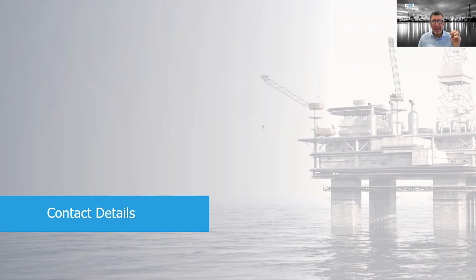They asked, do the glands have to be certified? If I remember correctly, this is somewhat of a sticking point. For circuits that contain a single IS circuit, meaning if we have a junction box with a single circuit coming in and a single circuit going out, the standard does allow you to use, and I want to double check this, basically the requirement of the gland is that it has to meet the impact requirements of 60079-0 and all that good stuff, but I don't believe it has to be a certified gland. I may be wrong on that, but that's with a single gland with a single circuit. And that's per the IEC standard.